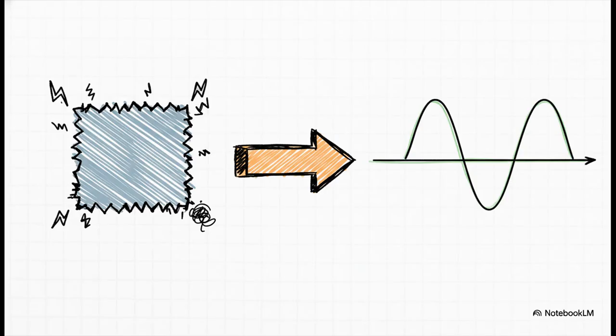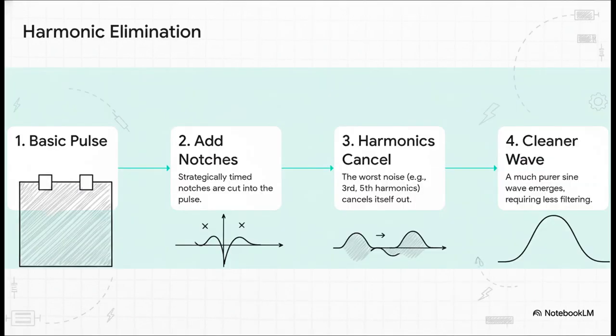And this is the goal. This is what we're after. We need to get from that crude, noisy square wave to this pure, clean sine wave, with none of that extra harmonic noise. And you can't just filter out the noise. It's way too strong. Instead, engineers use a technique that honestly feels like a magic trick, a way to cancel out the noise before it's even really created. It's called harmonic elimination.